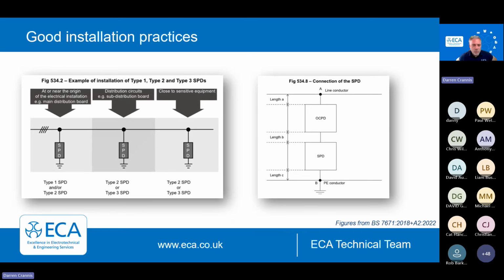Cable lengths. We talked very early on about making sure the SPDs are as near to the equipment as possible. I've seen these installed about 5 meters away from a distribution board, so they're not going to offer any protection at all. We need to keep these lengths as short as possible. Conductor length of these, we really want that down to the half meter.